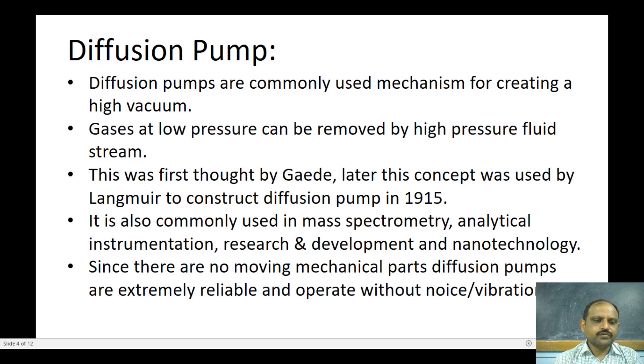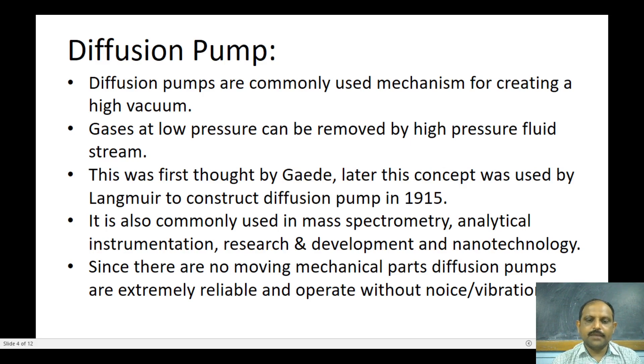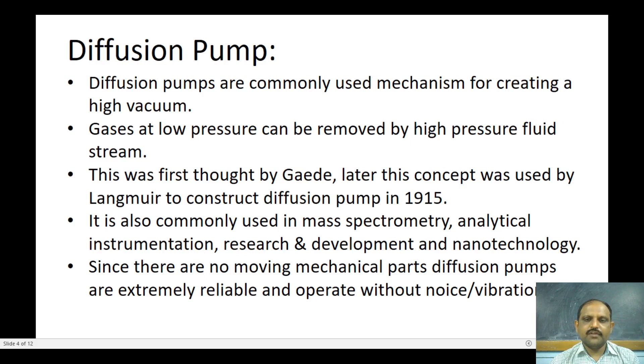There are no moving mechanical parts in the diffusion pump. If there were moving mechanical parts, there would be noise and vibration. Because there are no moving parts, the diffusion pump is extremely reliable and operates without any noise or vibration, which is why it remains widely used today in research and development and nanotechnology.